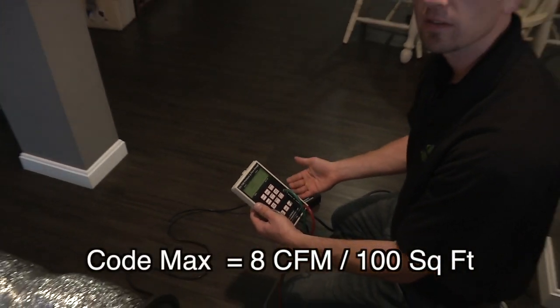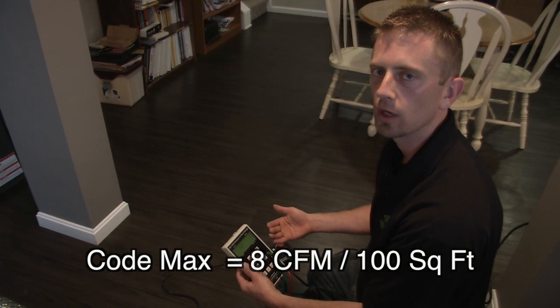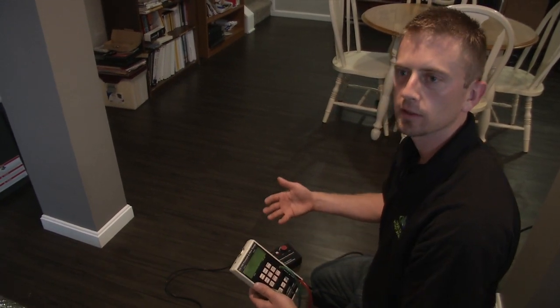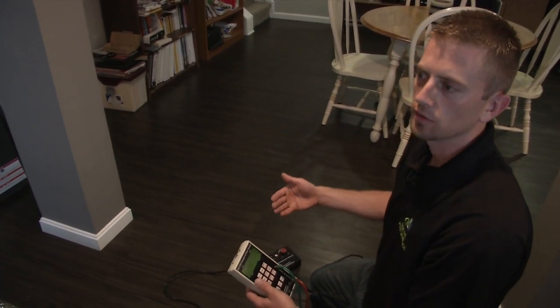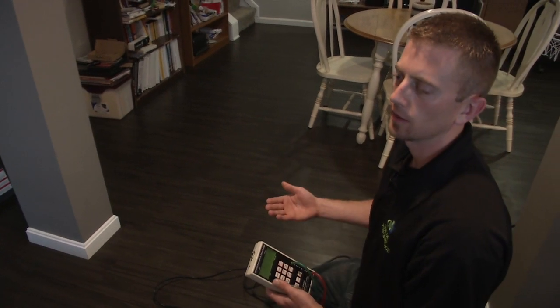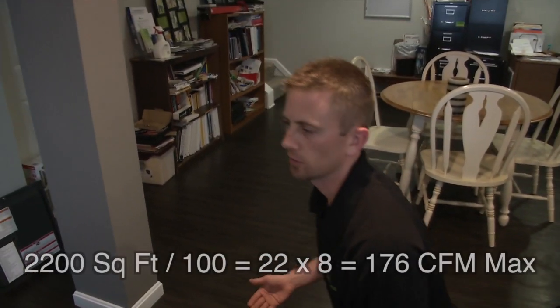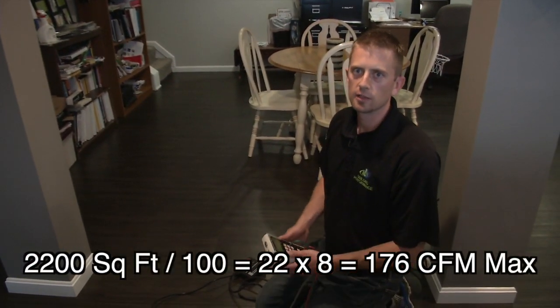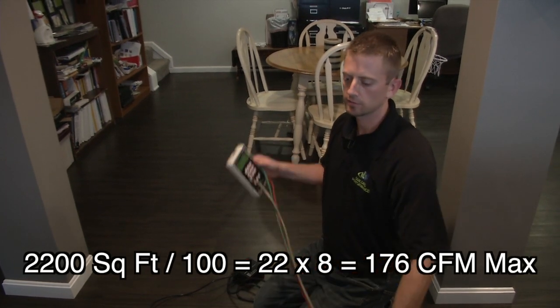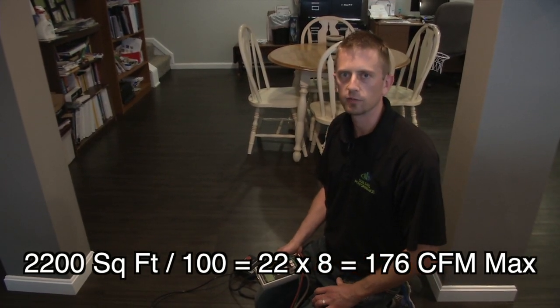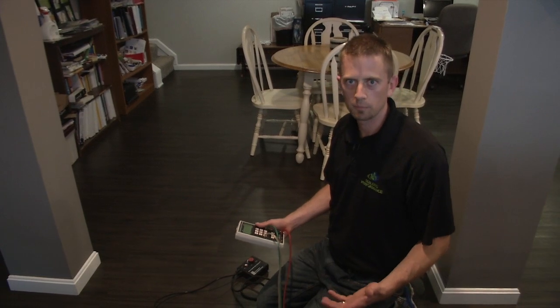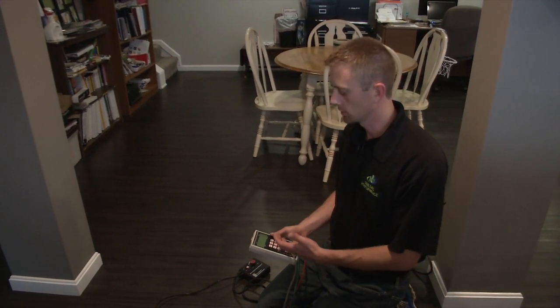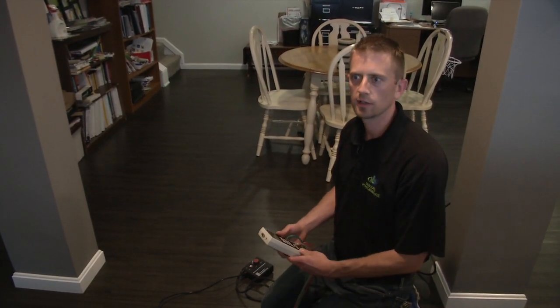The code maximum is 8 CFM per 100 square feet of area that the ductwork serves. So in this particular house, the ductwork serves about 2,200 square feet. So that would be about 160 CFM of leakage to outside that they could potentially have and still pass. So clearly this house passes.